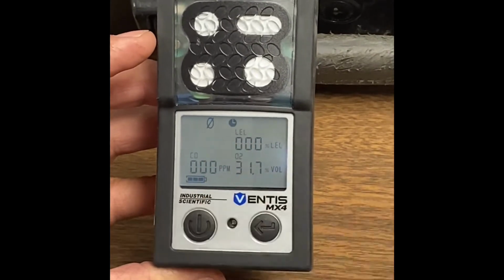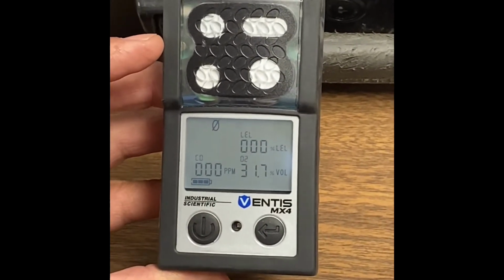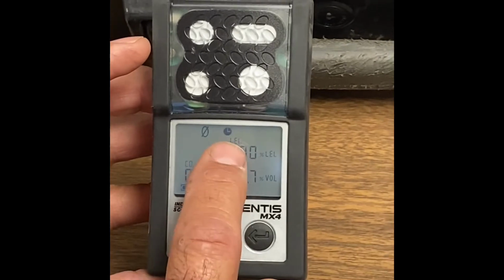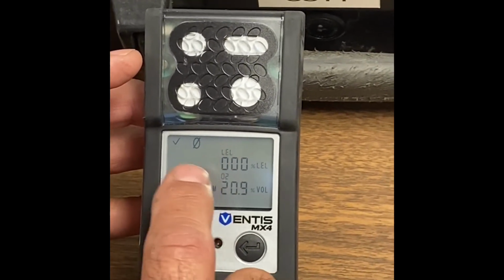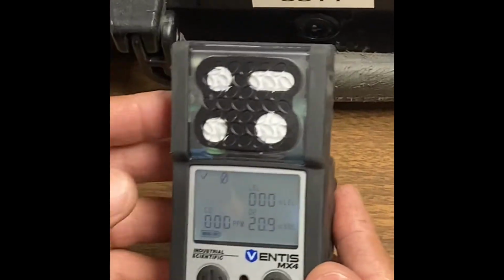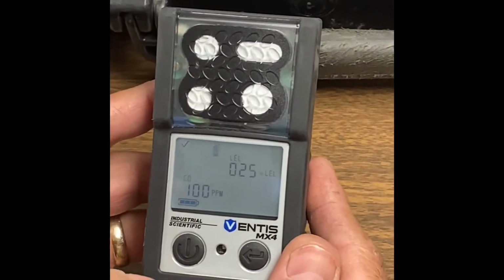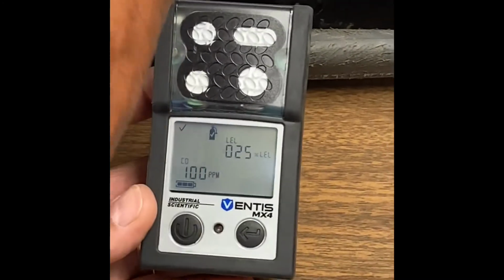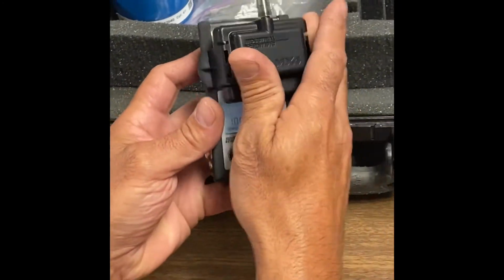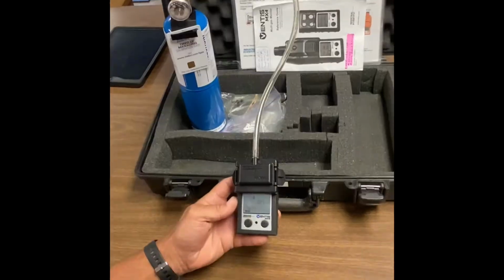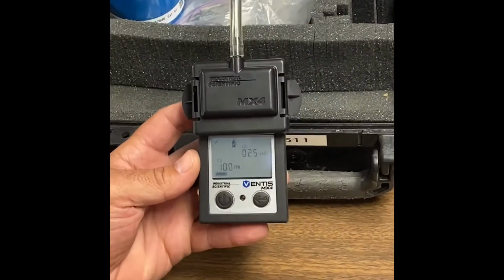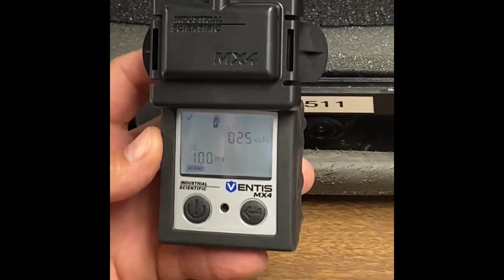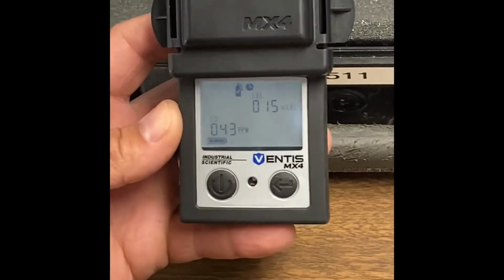Make sure you're in a non-contaminated area. And then take a look at that clock. Once it beeps and you see the check mark up in the corner, go ahead and press the mode button again. You'll see the tank flashing. Go ahead and attach your calibration cup, turn on your gas, and you're going to see these two numbers start going up, the LEL and the CO.